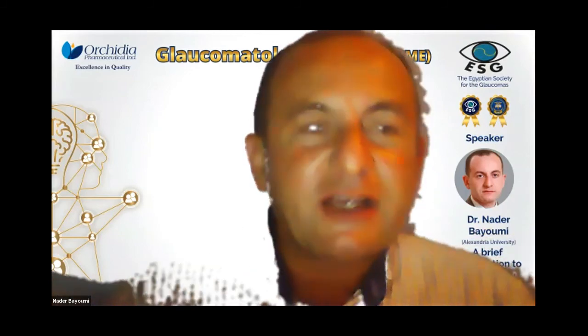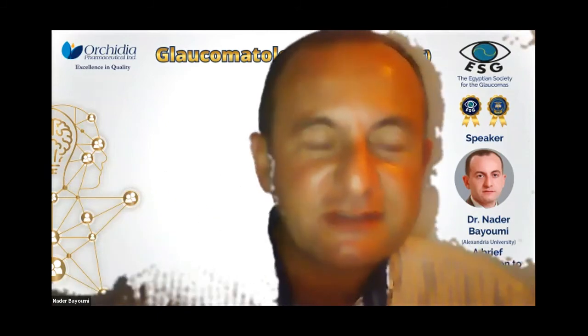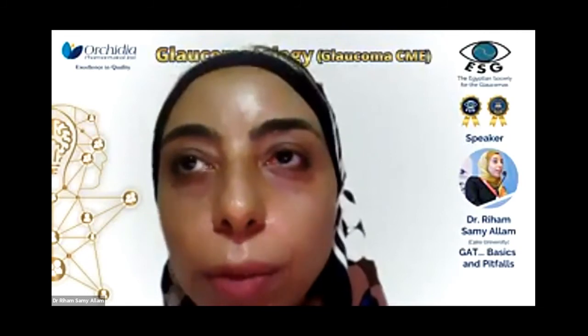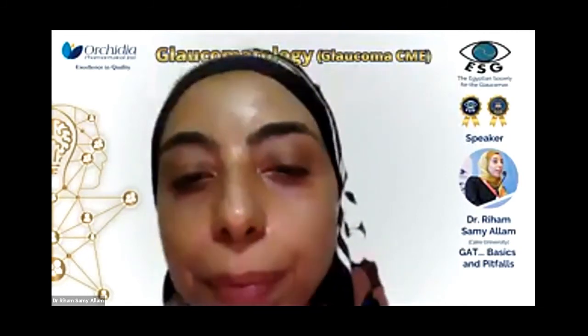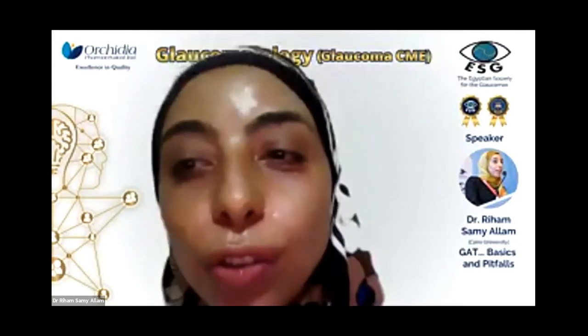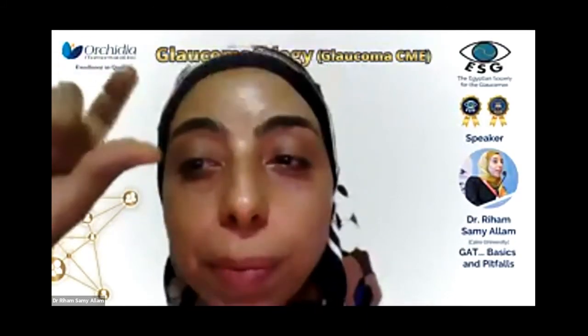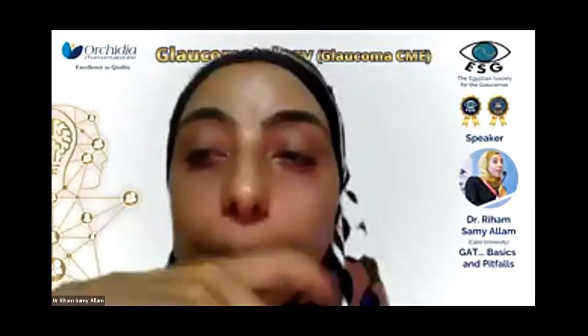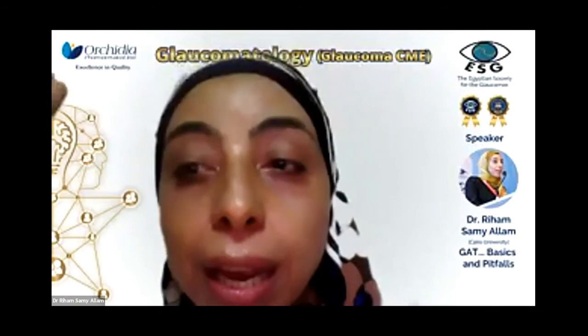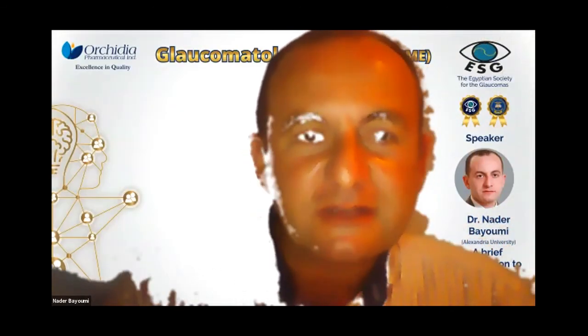Okay. One last issue: could you explain to our audience how an increased corneal thickness from corneal edema would result in a falsely low IOP measurement? Yes, this is not related to the thickness itself. This is related to the corneal properties as well. The cornea yields with the applanation, so you need less force to flatten it, and so the pressure reads low. It's not related to the cornea being thick. The cornea can be thick but edematous, like in pseudophakic bullous keratopathy, for instance. So it would absorb the pressure of the tonometer. It will attenuate it, actually. You need less pressure to flatten it.